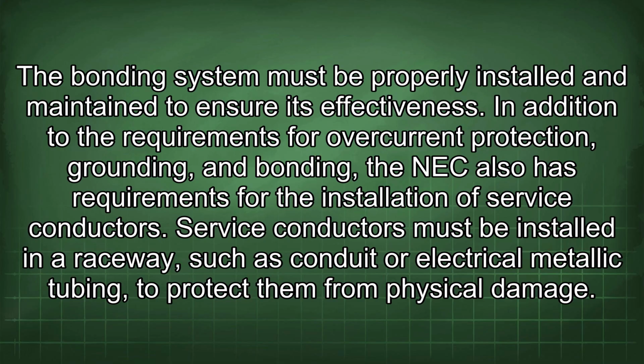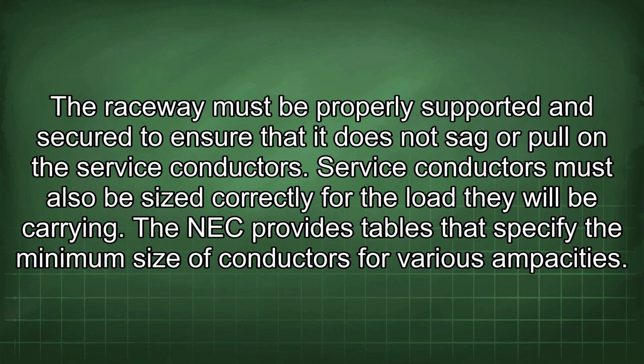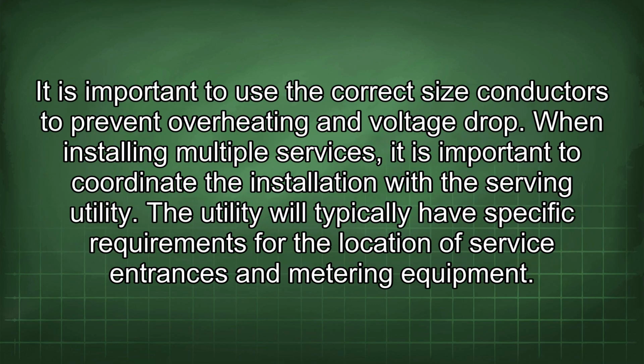In addition to the requirements for overcurrent protection, grounding, and bonding, the NEC also has requirements for the installation of service conductors. Service conductors must be installed in a raceway, such as conduit or electrical metallic tubing, to protect them from physical damage. The raceway must be properly supported and secured to ensure that it does not sag or pull on the service conductors. Service conductors must also be sized correctly for the load they will be carrying. The NEC provides tables that specify the minimum size of conductors for various ampacities. It is important to use the correct size conductors to prevent overheating and voltage drop.